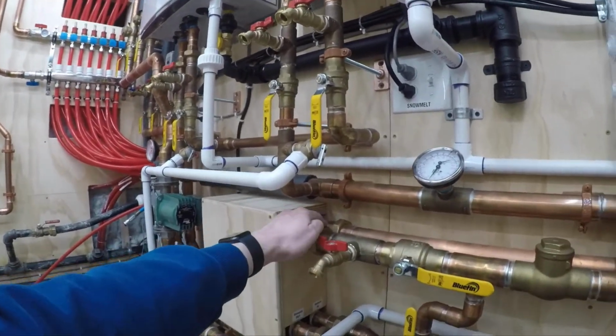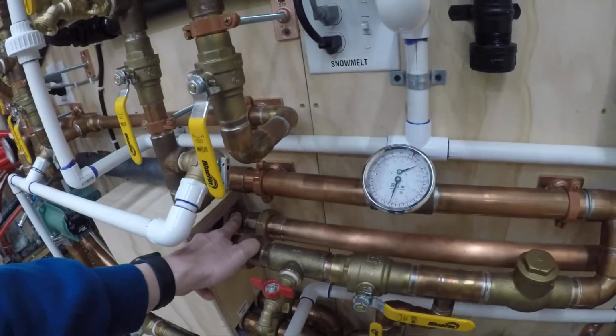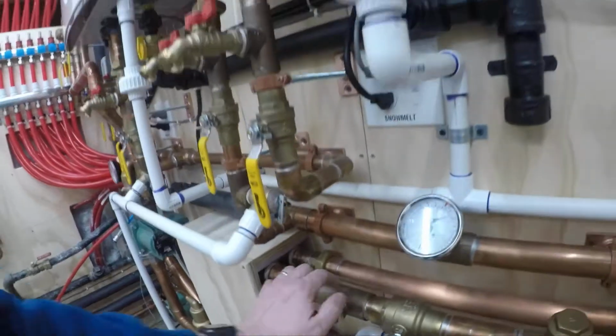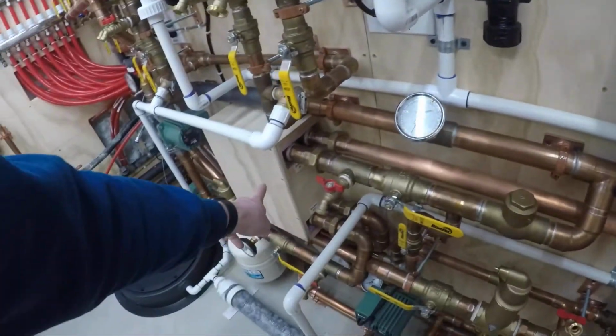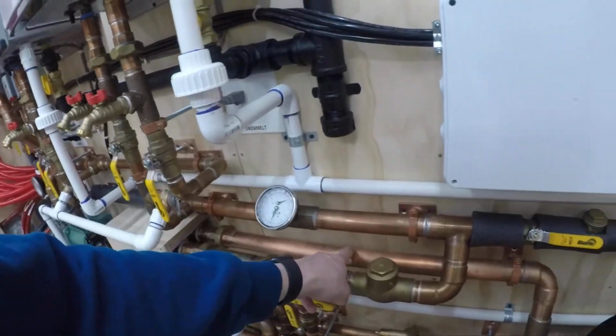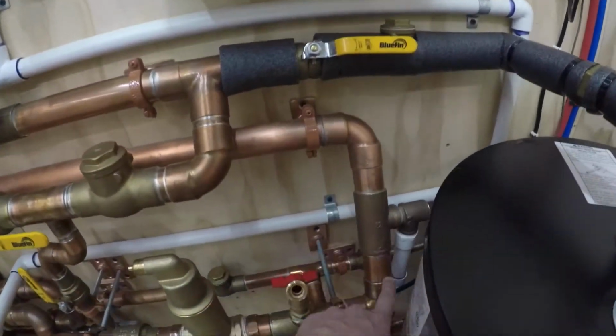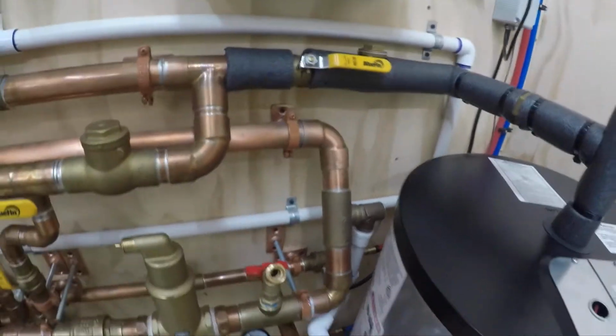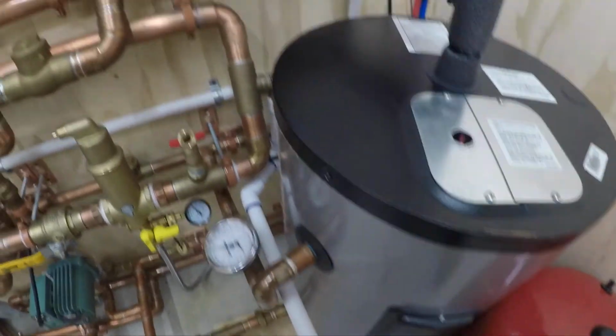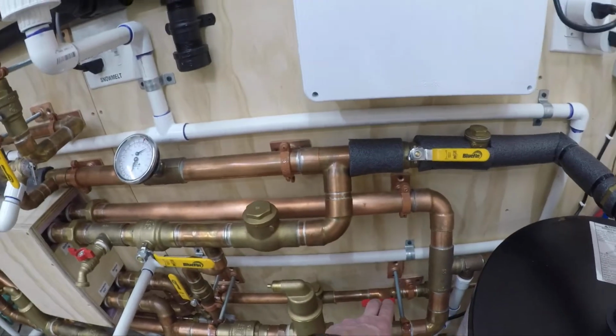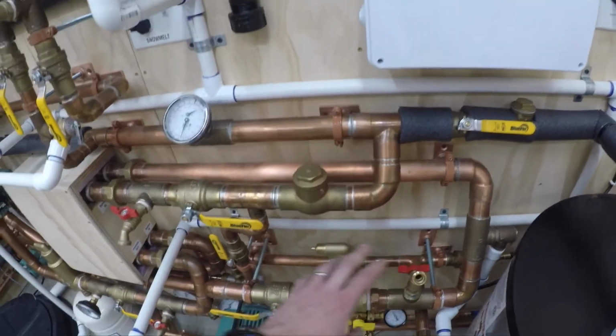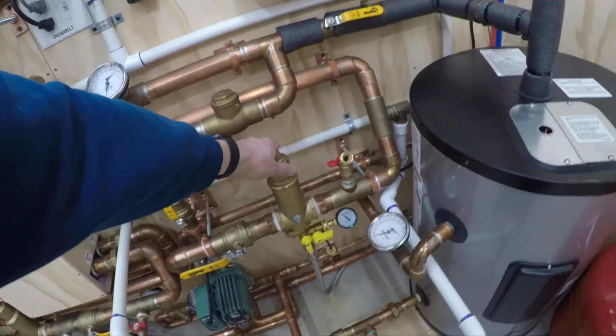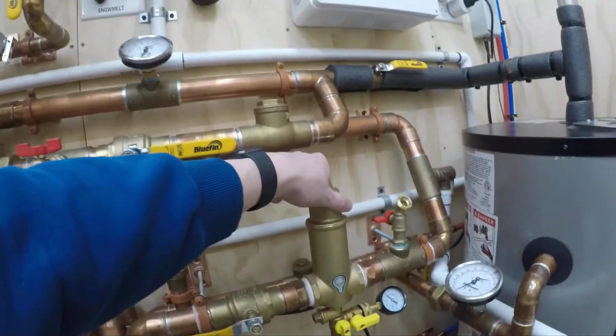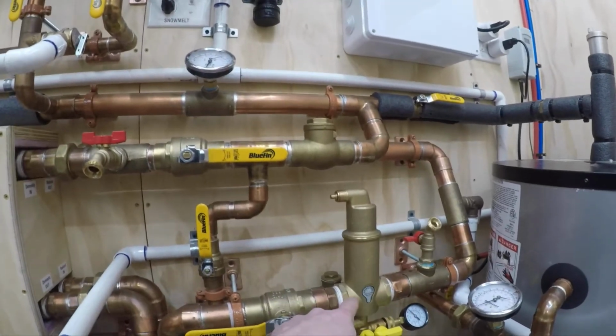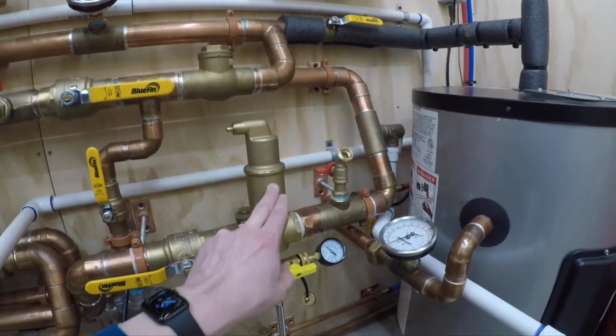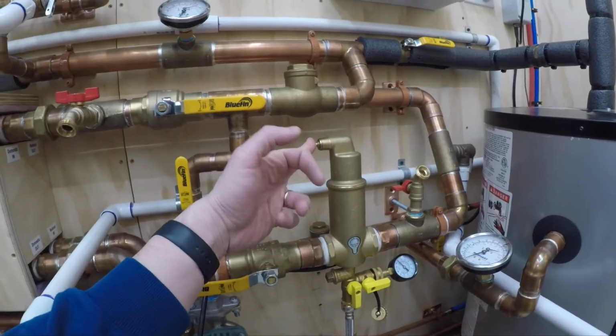So the water, I keep saying water, the glycol coming out of the radiant outside of this flat plate will come out here with as much heat that it can steal from the primary loop side. So this glycol will be heated, comes out. I have a pressure and relief valve there, which I just plumbed out now so that I could put a bucket under it when I was filling it. I have a purge valve here, which comes in very handy when you're filling the system. Spirovent, which will take all the air out. It's basically a micro bubbler. So, any little air bubbles that pass through here get caught on these grates and they fizzle up inside here, and then they just bleed out through here.